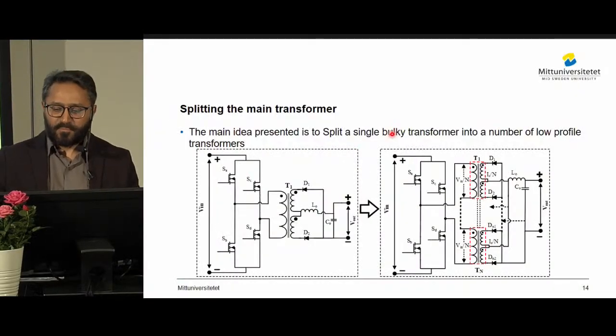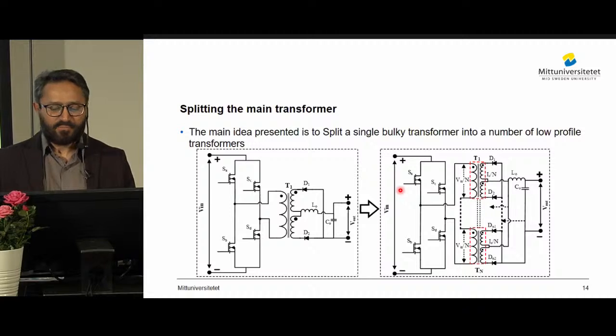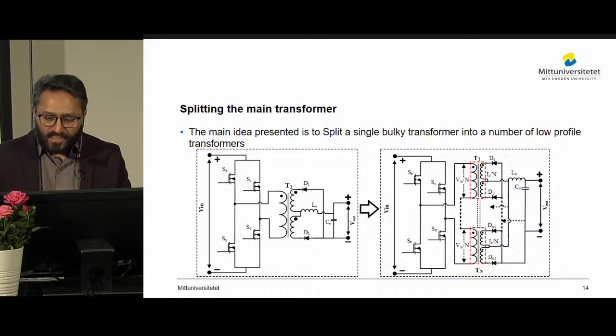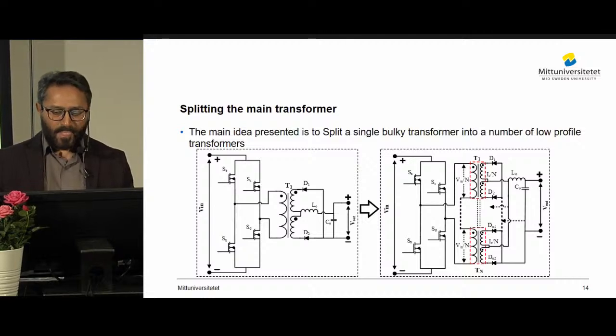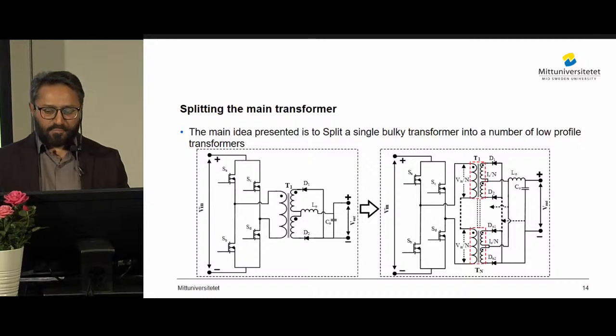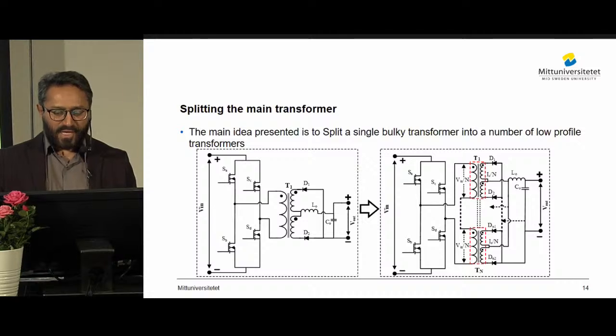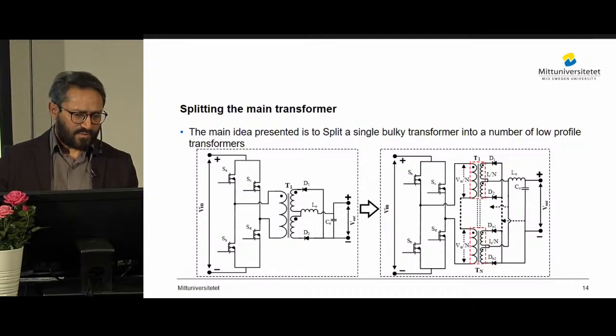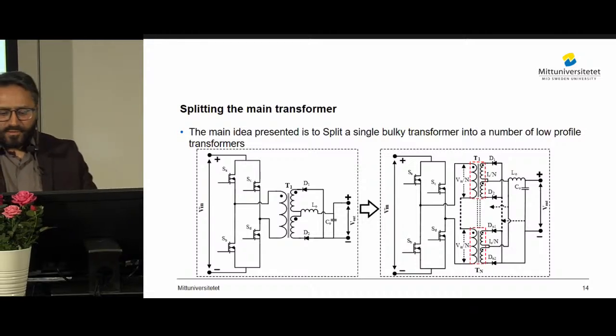In the first design phase, the idea to split the traditional bulky transformer into several transformers has been presented. For example, a typical single transformer in a full bridge converter is transformed into n number of transformers. Here the primary windings of the transformers have been connected in series and the secondary windings have been connected in parallel. In this way, the applied voltage stress on each transformer will be reduced by the number of transformers. And similarly, the load current is shared by the n transformers.